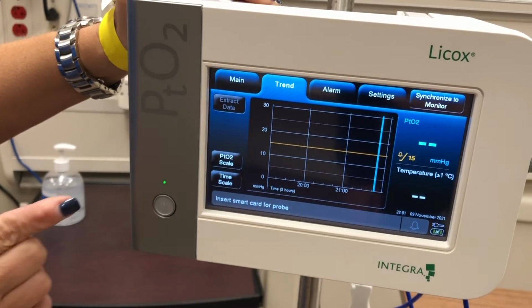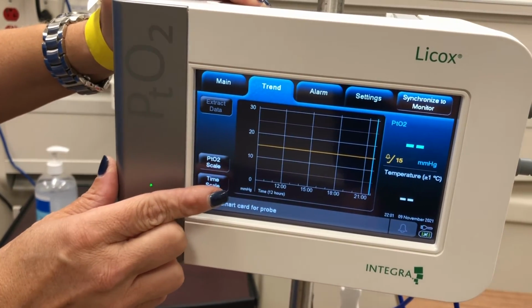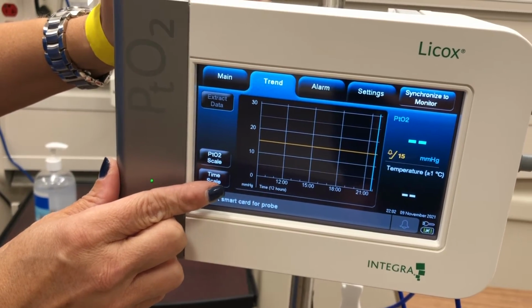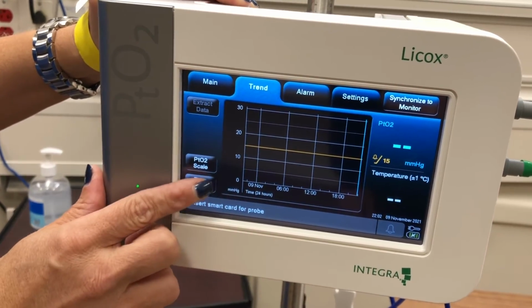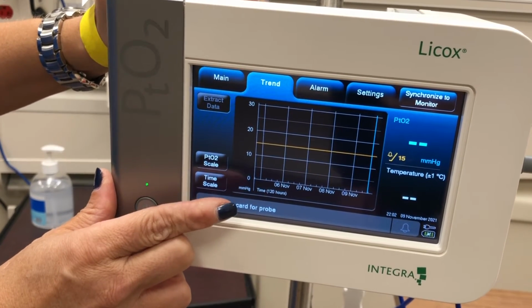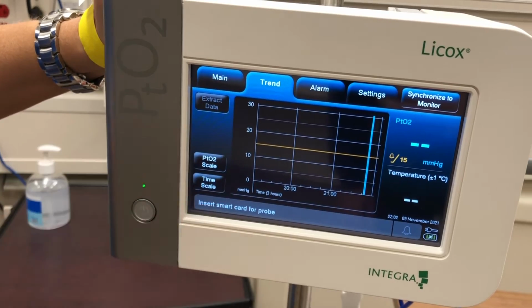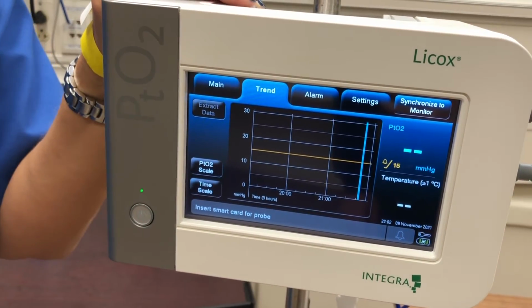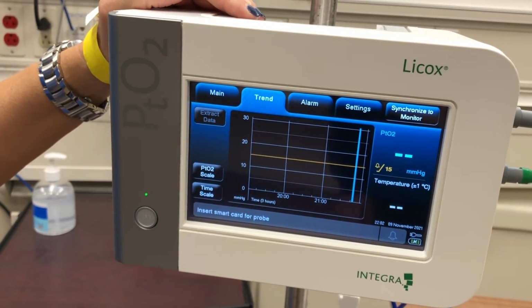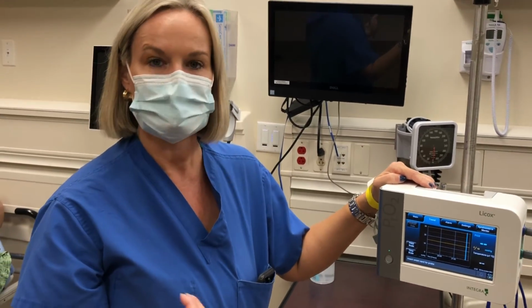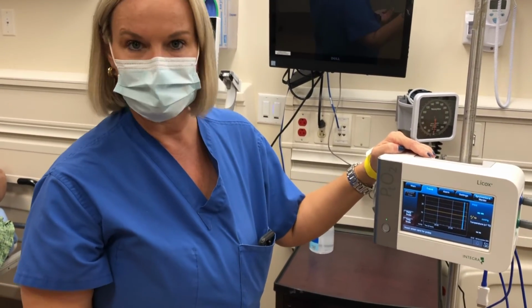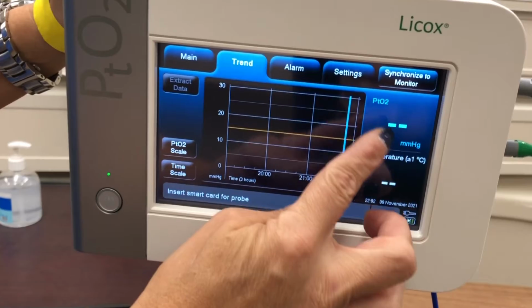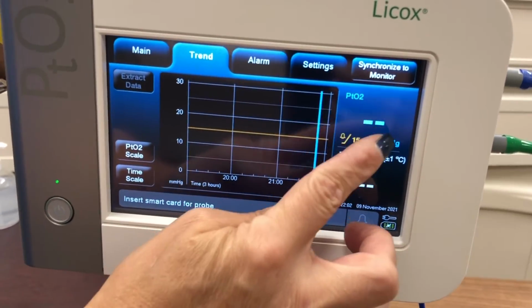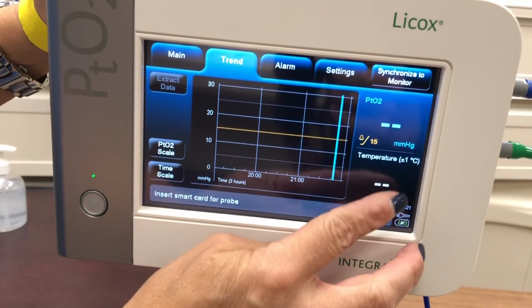Across the bottom is my time scale. I can press that, and I'm looking now at what looks like 12-hour increments, and it tells me what the interval is down here: 24, 48, and then 120, which is 5 days. And I'll go back to just the 3-hour increments here. A Licox probe is never going to be inserted for more than 5 days because per the manufacturer, aka Integra, we suggest that you change it if you want to leave it in longer than that. So 5 days is the maximum that we have given to the FDA as what it's approved for. Over here on the trend screen, you're also going to be seeing continuously whatever is being transmitted for the actual brain tissue oxygenation and the temperature.